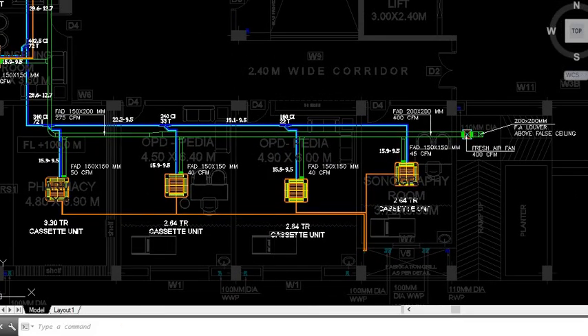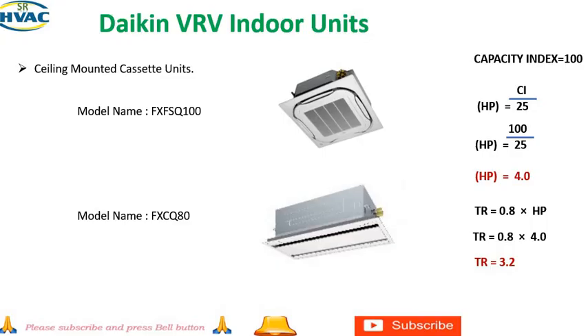Friends, let's see, our next topic is Daikin VRV indoor units. We will see the indoor units and their capacity index and their ports. First we will see the ceiling mounted cassette unit. The model is FXFSQ100. It may be 63, it may be 50 or 125 or 140. It depends upon what is your need. This is the 4-way cassette unit, and this is the capacity index 100.